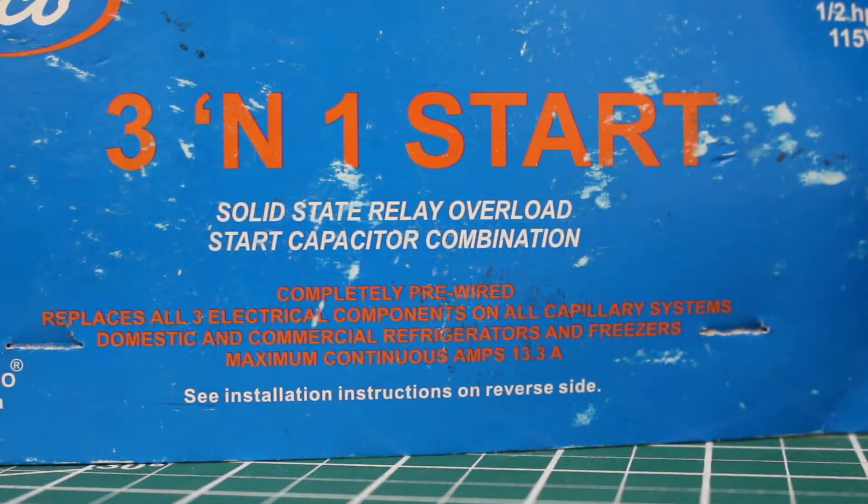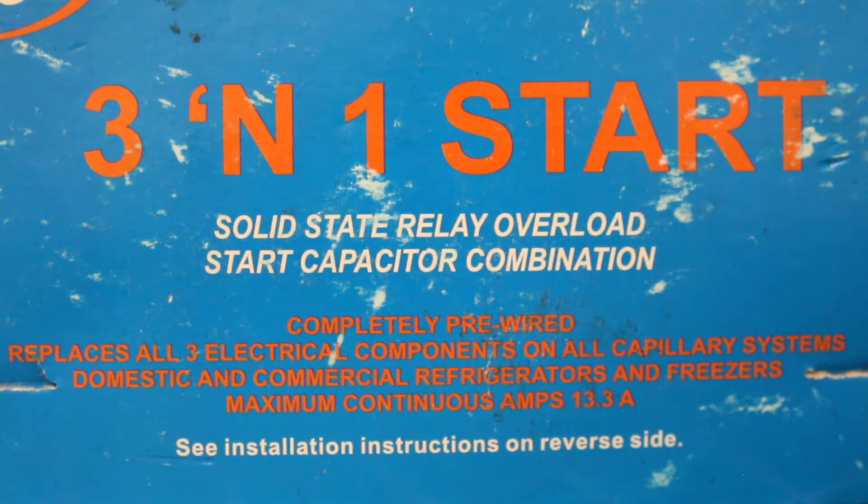This kit specifically is made by Supco and comes in various sizes. The 3-on-1 comes from three components being in one — a solid state relay, an overload, and a start capacitor, all built into one. This control is completely pre-wired and replaces all three electrical components on all capillary tube systems. It can be used for domestic and commercial refrigerators along with freezers.